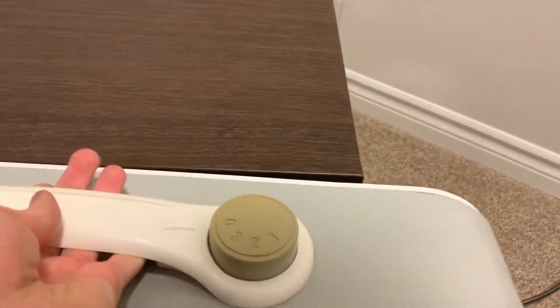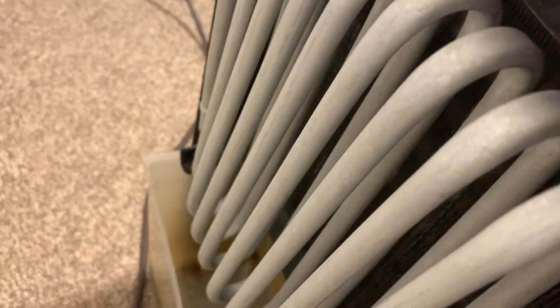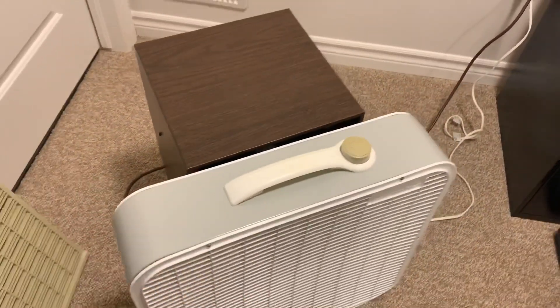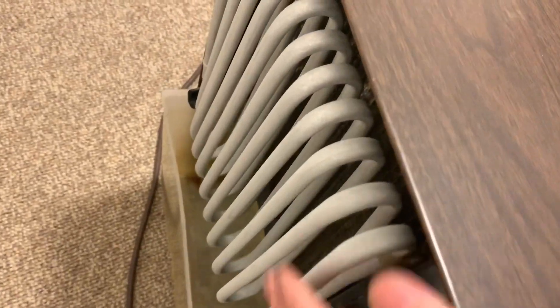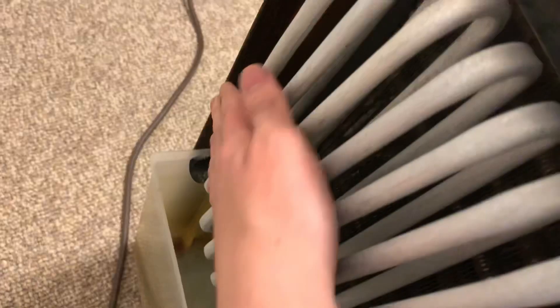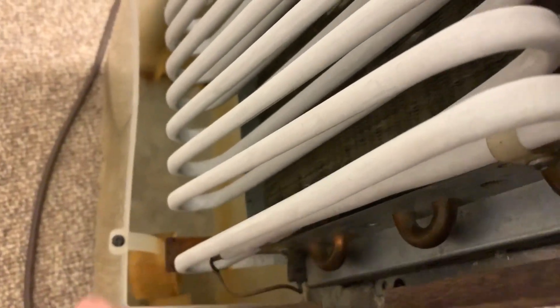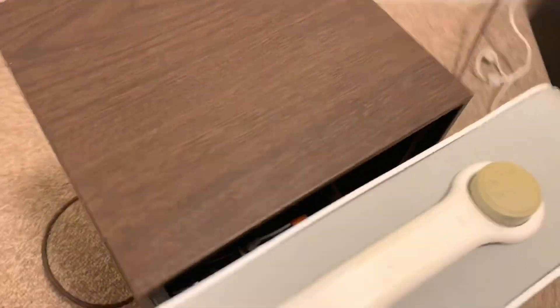Now I'm going to place the fan on the front and crank it onto low speed. That's drawing plenty of air through the back. Unfortunately I don't have an infrared temperature gun, so I won't be able to show accurate temperature readings of the coils. But speaking of that, it's actually getting cold already — it's starting to get cold right where the charge is flowing in. Oh yeah, that's ice cold already. It takes time for the refrigerant to make its way through the entire coil, but it seems to be working — and that's a good sign.